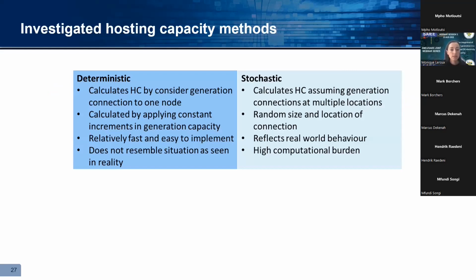The first one was a deterministic method, which calculates the hosting capacity of a network by considering generation that is only connected to one node, and then increasing that generation by a constant increment, and then seeing where violations on the network in terms of voltage and thermal limits are seen. This method is quite fast to implement and quite easy, but unfortunately it does not resemble a situation in reality where you would see multiple generators connecting on the same network, as this only considers generation at one busbar or at one node.